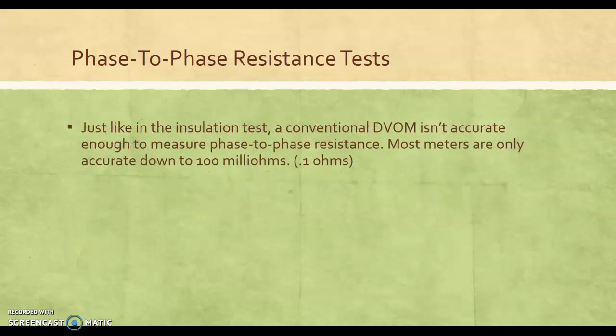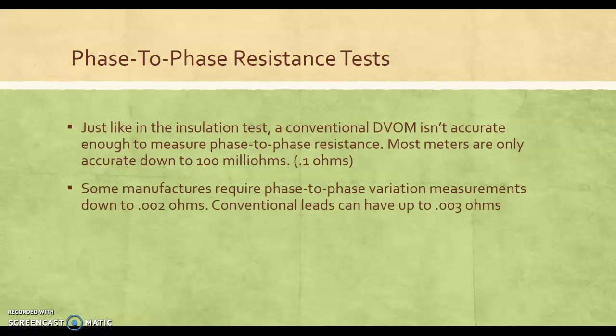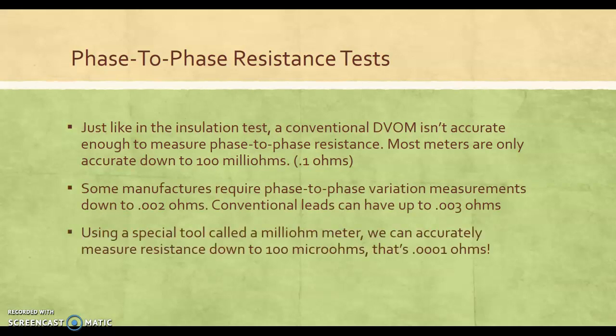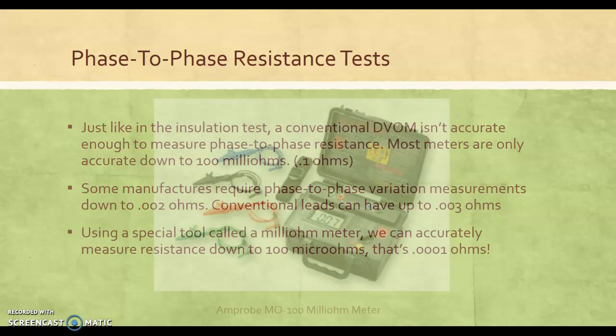So basically the DVOM or DMM isn't accurate enough to measure phase to phase. Although the meters read milliohms, they're not accurate down to milliohms. You're looking at 0.1 ohms, that's 100 milliohms, and we're looking at readings that could be down as low as 30 milliohms. So you use a phase-to-phase balanced milliohm tester. I'm going to show you what that looks like.